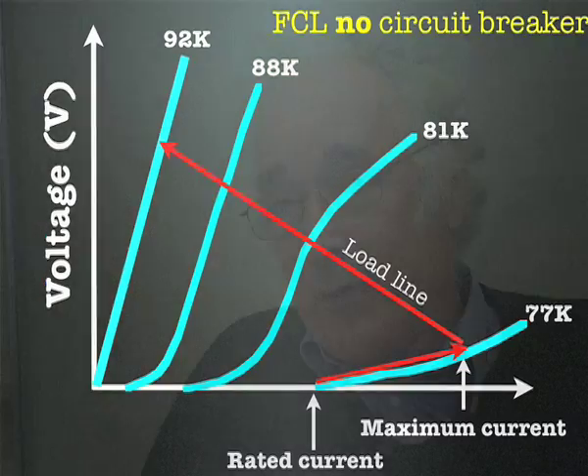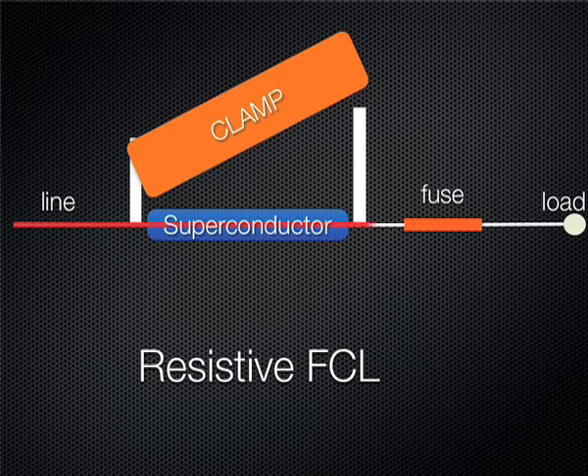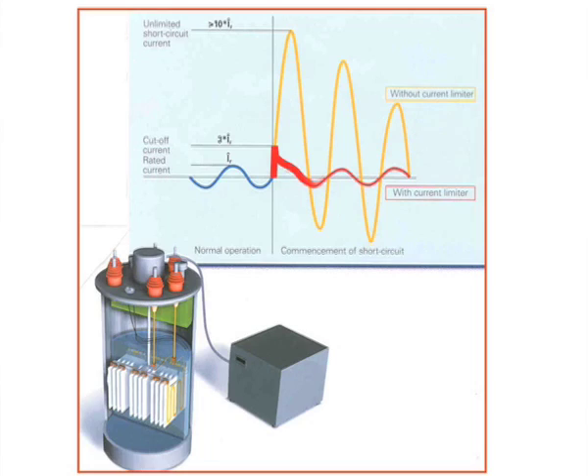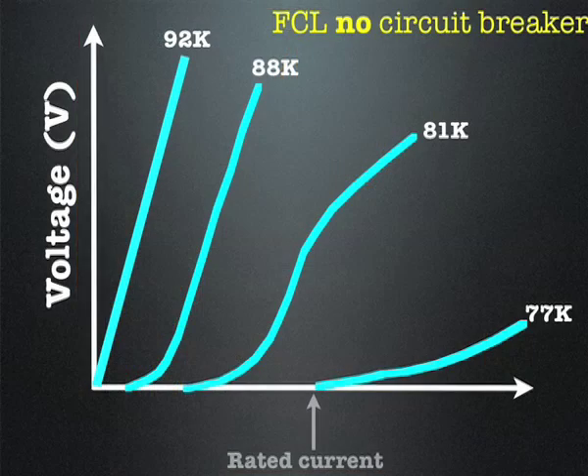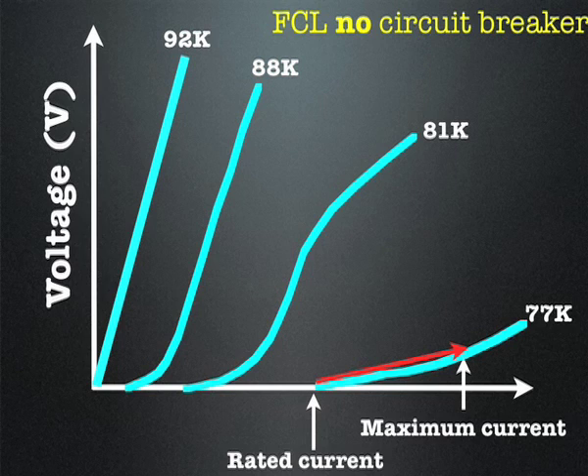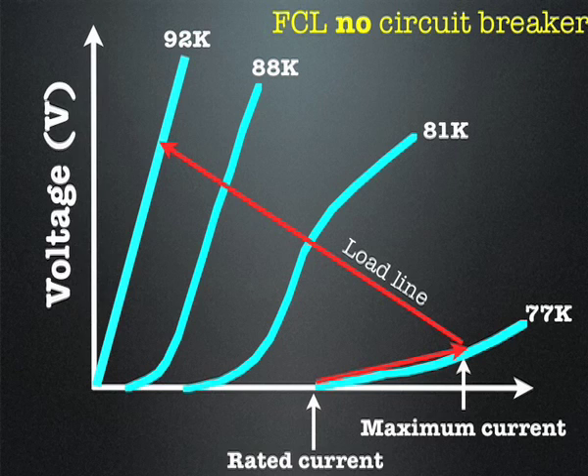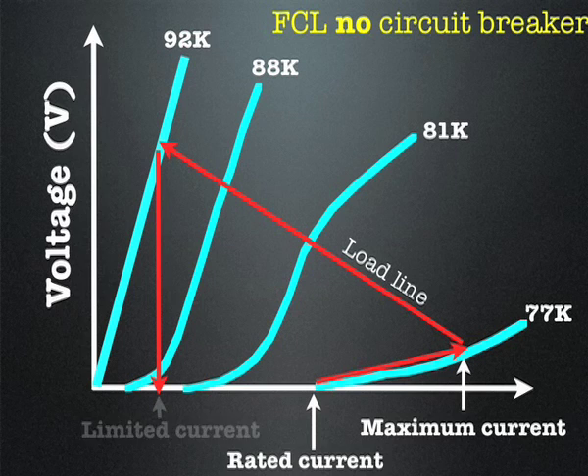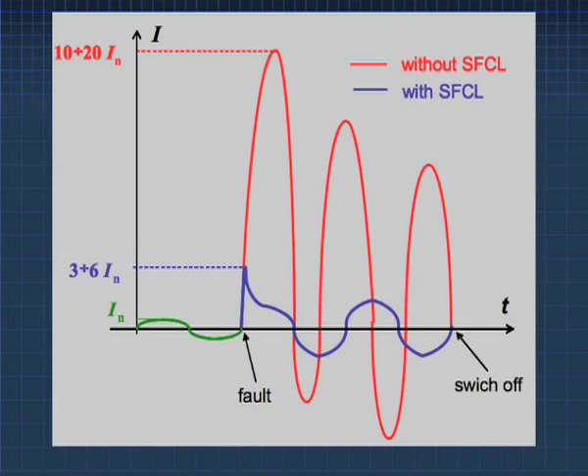We start off not on the load line because the material is superconducting. As soon as we get a short circuit and a fault, we go up the VI characteristic until we reach the load line. At that point it's heating up very rapidly, so it moves back along the load line along the curves of gradually increasing temperature until it reaches the normal state. It may go higher, but the resistance won't change so much after that. Once it reaches the normal state, the current below that is the current at which it stabilizes.